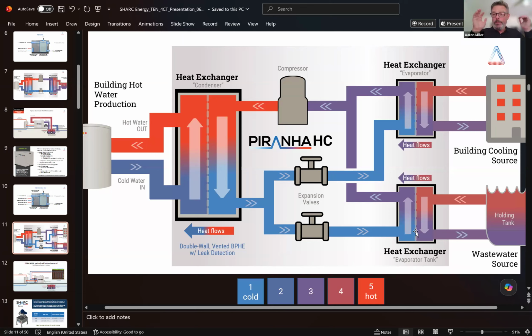Imagine now summertime flips the script. Your tank is still about 68, 70 degrees year round, but now your ground loop, your geothermal loop, is like 95 degrees because every apartment is pushing heat into that loop. So when the Piranha turns on, it looks at 70 degrees and 95. It's like, oh, I'm going to pull off this. And then again, throughout the year, it just picks whichever one's richer. So again, it's a really, really cool off-script way to now make hot water using all electric principles.